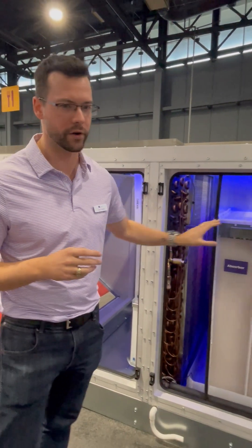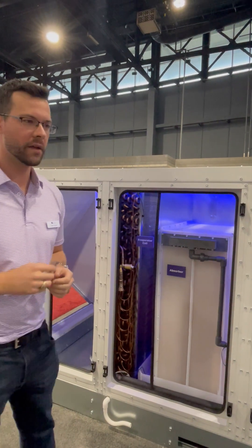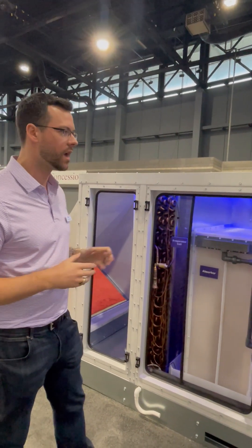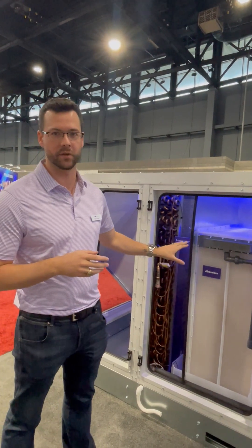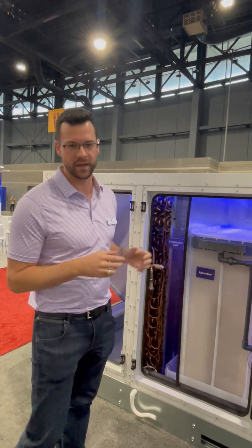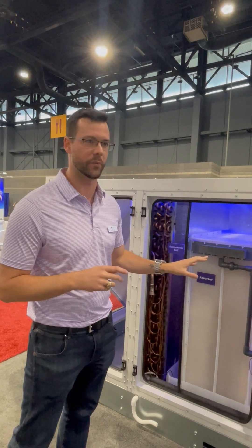From there, we're interfacing our saturated air with our desiccant media, our absorber. This is where we're going to ride our enthalpy line. There's a conservation of energy happening — we're drawing moisture out of the air while simultaneously releasing heat back into that airstream. So rather than a hot gas reheat coil with a typical DX system, you're not overcooling that air. You're leveraging the exothermic nature of desiccant to draw that moisture out of the air while simultaneously releasing heat to hit your final neutral air temperature.